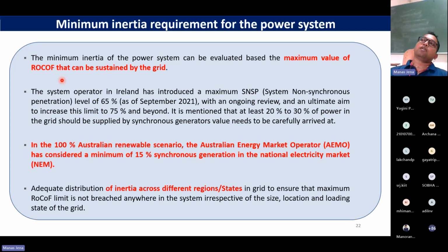So now I essentially go again from how much inertia I have, to what is the minimum inertia requirement, to what is the maximum rate of change of frequency (RoCoF) your grid can survive. So what are the operators around the world doing? The system operator in Ireland has introduced a maximum SNSP, the system non-synchronous penetration level, of 65% as of September 2021, with an ongoing review and an ultimate aim to increase it to 75%.